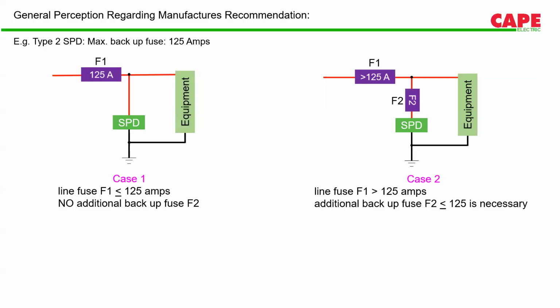Similarly, in the second case where F1 is greater than 125 amps, we need a second backup fuse which we can call F2. Now, there are two conditions which we have to follow here. First, F2 is required when F1 is more than 125 amps. Second, F2 should always be less than or equal to 125 amps, as the manufacturer has suggested.